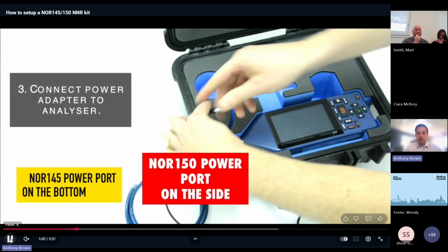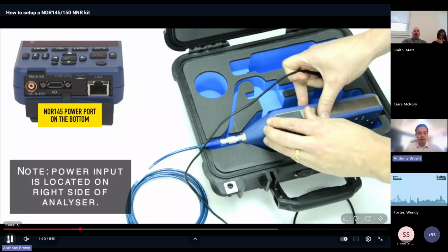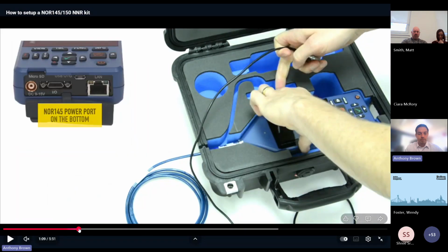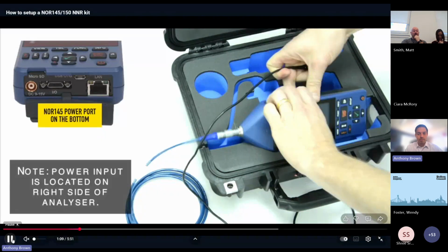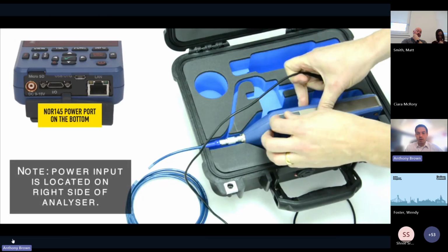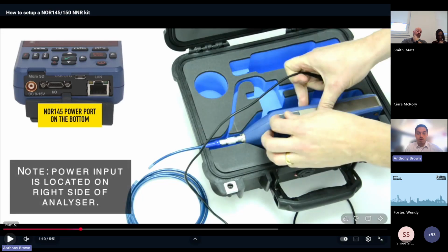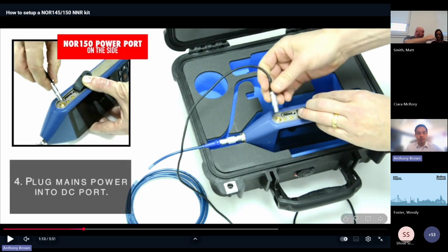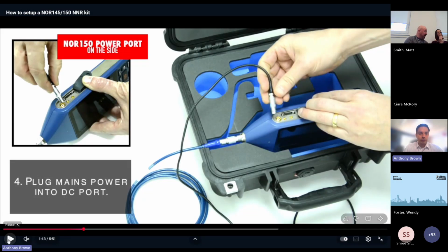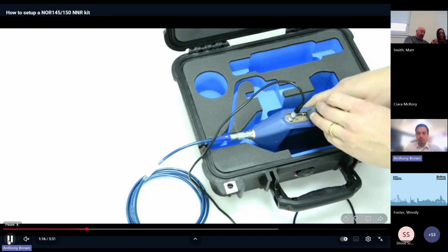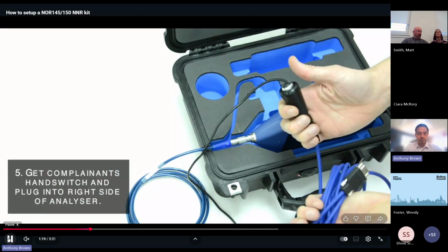And then once you've connected the microphone cable, this shows the connection of the power supply. So this will either be on the bottom of the meter if you've got a 145. So on the left, there's a power socket on that side. If you've got the 150, it will be as the right-hand side of this video right now, where there's a flap on the side that you release. And then you can see you can place the connector for the charger into the side of the meter. And hopefully you've kind of worked that out already. If it is your first time, then I'll just give you a second to set that up.